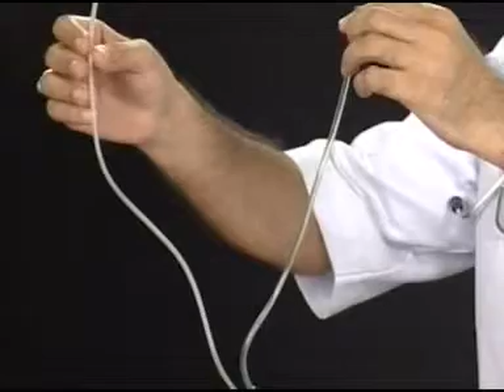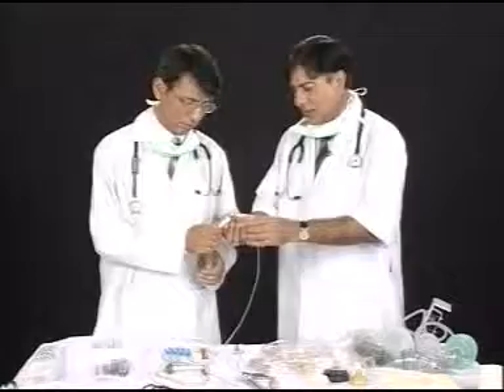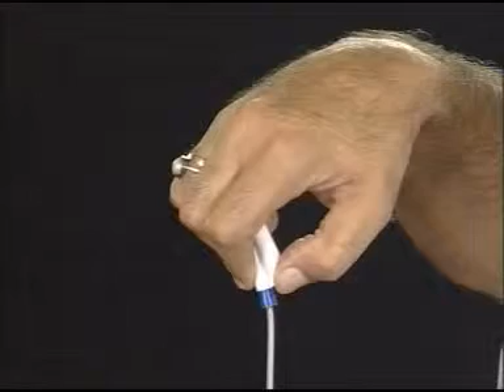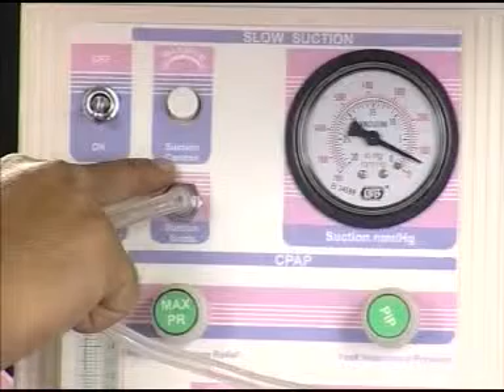Then we use several catheters of different sizes, but generally the size of the catheter should be about 10 French or more, and preferably they should have a thumb control. By having a thumb control, it is easier for a person to control the negative pressure which is generated by the machine. Ideally the pressure should not be more than 100 centimeters of water.